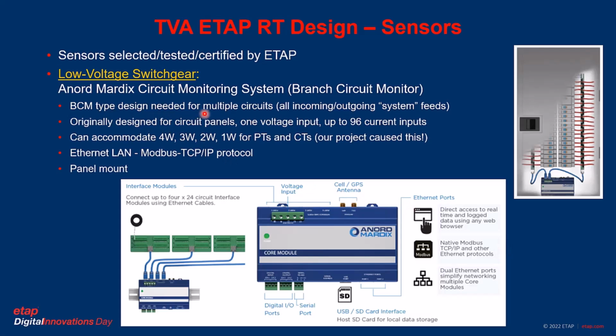So its design is what you would need for having multiple circuits. We can get all the incoming and outgoing system feeds at this location. As I said, these were originally designed for circuit panels with 1 voltage input and up to 96 current inputs. Now we don't have 96, we only have about 9. But these also can accommodate 4-wire, 3-wire, 2-wire, 1-wire type hookup for PTs and CTs. They have a built-in Ethernet LAN module that can do the Modbus TCP/IP protocol, and these are meant for panel mounting.